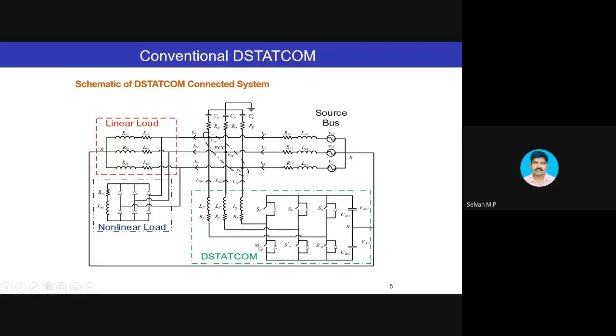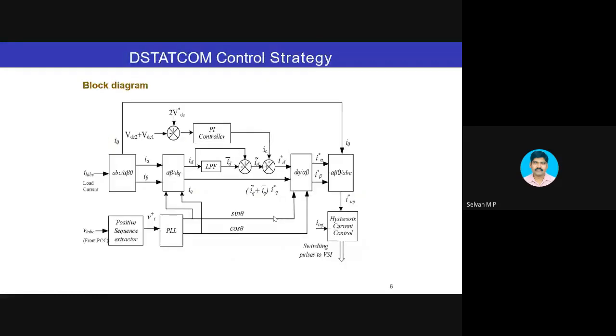But this can provide me a reactive power which can be a variable one. If these loads are variable in nature, I need a variable reactive power source. This STATCOM can be operated as a variable reactive power source to supply reactive power. So the control is going to be like this. I will take the load current drawn by the load. I will do the ABC to DQ transformation.